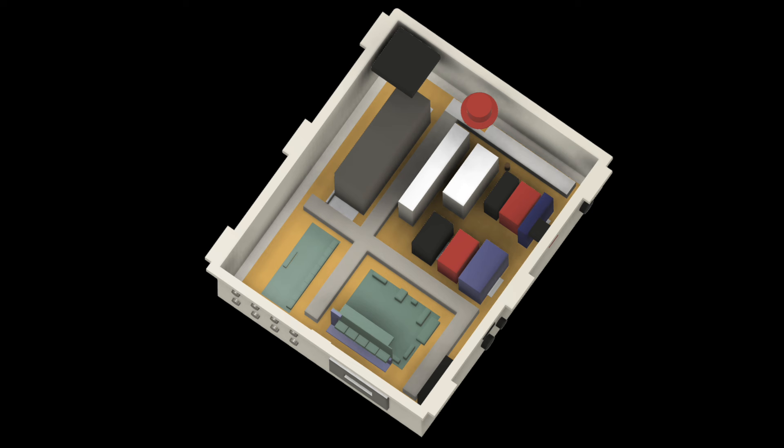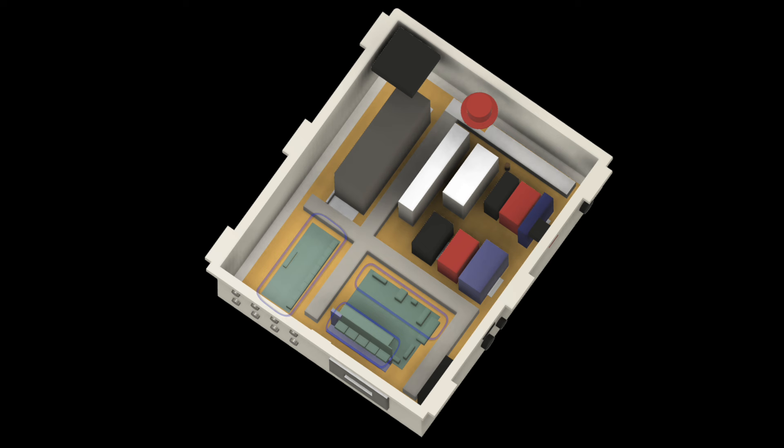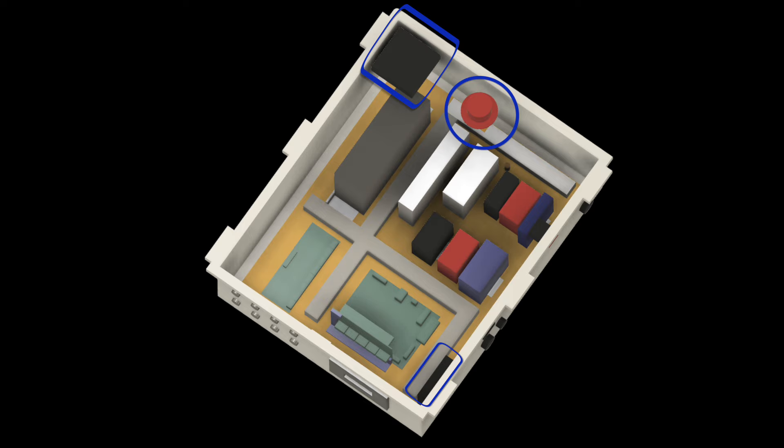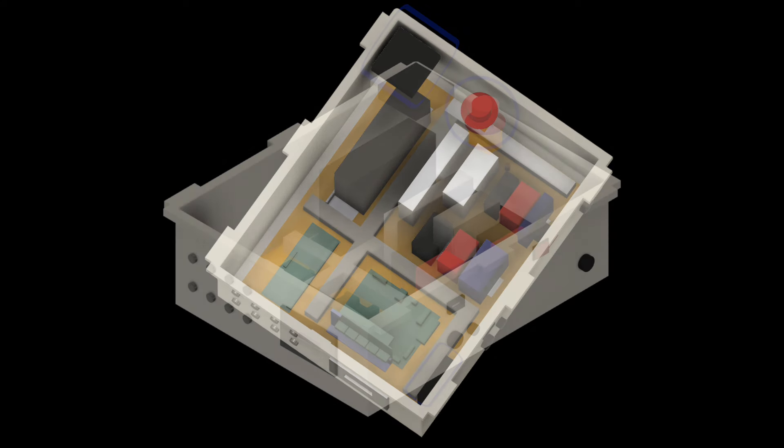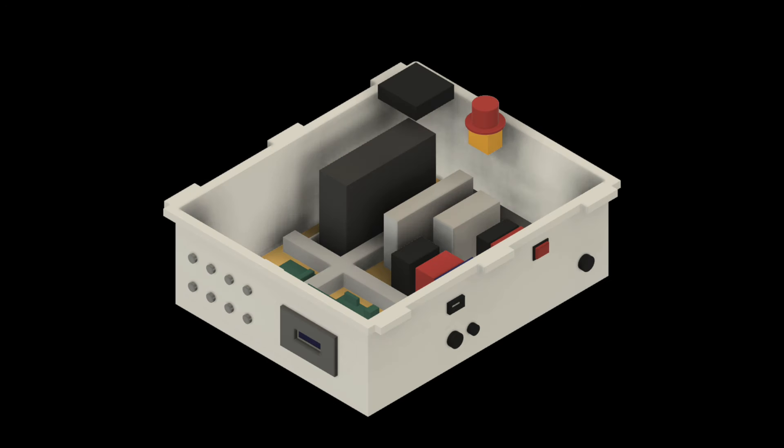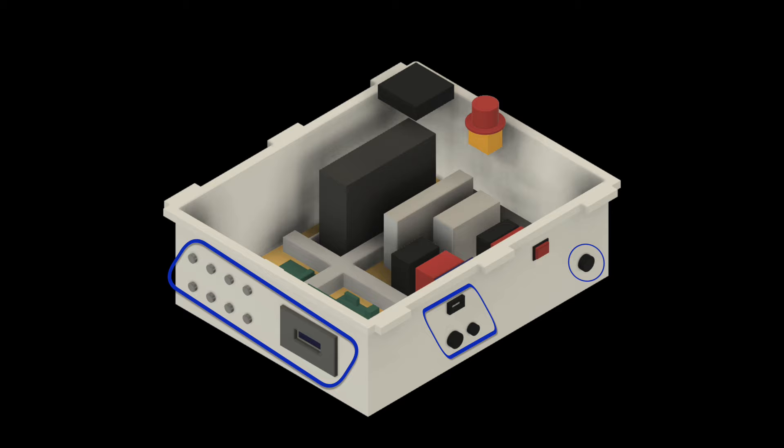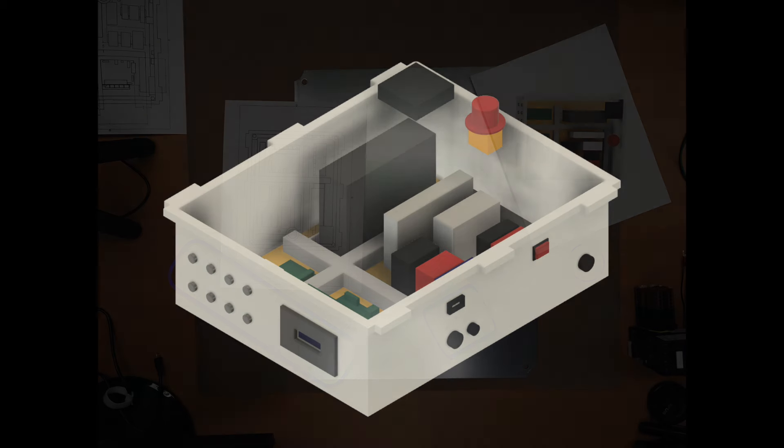Building a 3D model rather than just a 2D plan allows the spacing and placement of components to be more effectively visualized. Pay attention to board connections to allow cables to be plugged or unplugged. The fan and emergency stop locations can all be verified for clearance and effectiveness. The cable entry locations, covers and supports can also be checked.